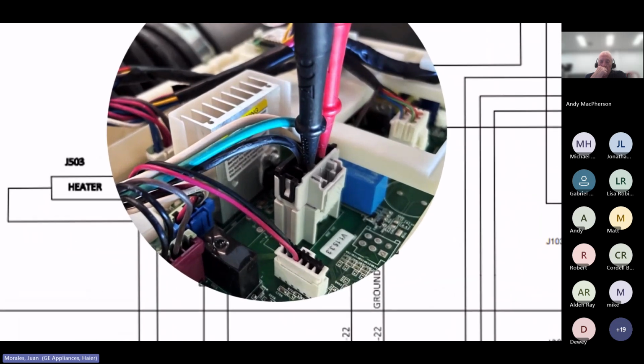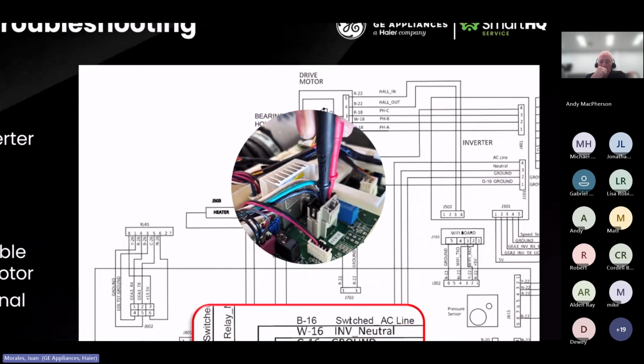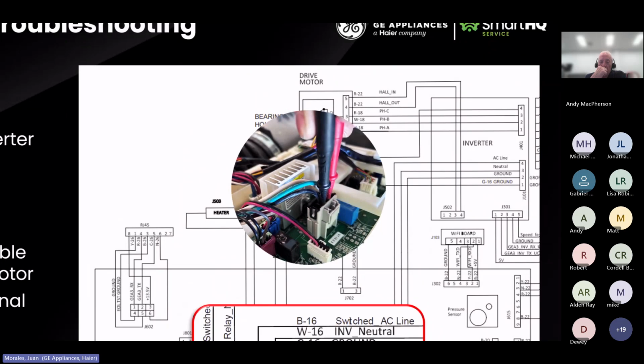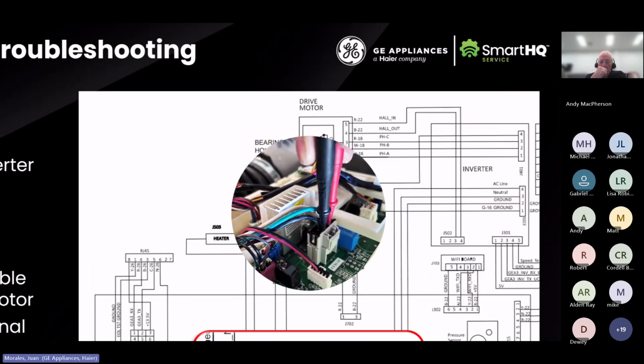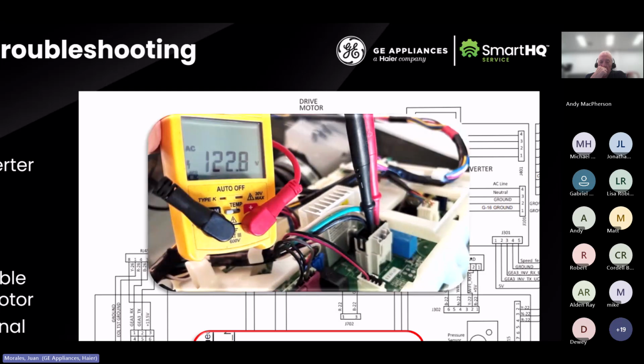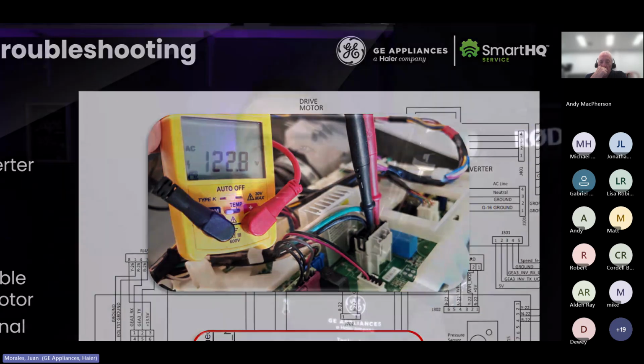So there's the connector right there. You would put your leads between pins 2 and 3, which is your line and your neutral. And then you would activate your motor, either the spin action or the agitate. And what you should get on your multimeter is 120 volts AC. So it's going to go from 0 to 120 the minute that you activate a spin or agitate action. Now, all of this is going to happen while you're with the machine.